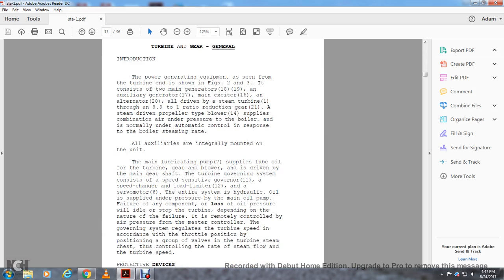Auxiliary equipment is integrally mounted on the unit. The main lubrication pump supplies lube oil to the turbine, gear, and blower, and is driven by the main gear shaft. The turbine governing system consists of the speed sensitive governor 11, speed changer and load limiter 12, and the servo motor 6. The hydraulic oil for the entire system is supplied under pressure by the main oil pump. Failure of any component with the loss of oil pressure will idle or stop the turbine, depending on the nature of the failure.